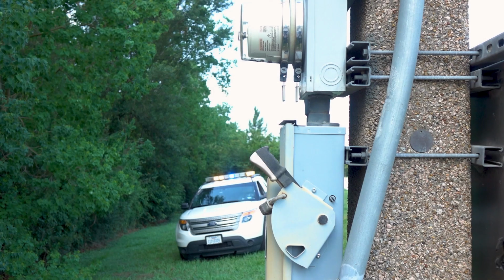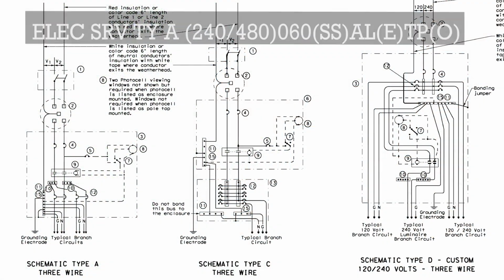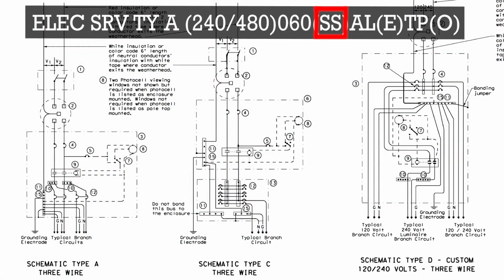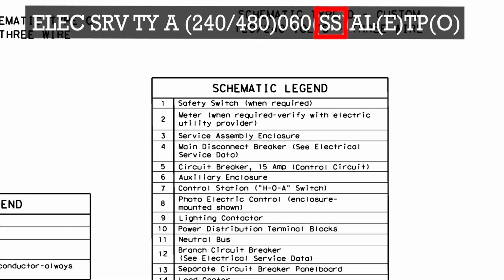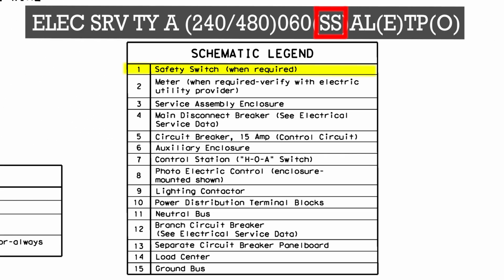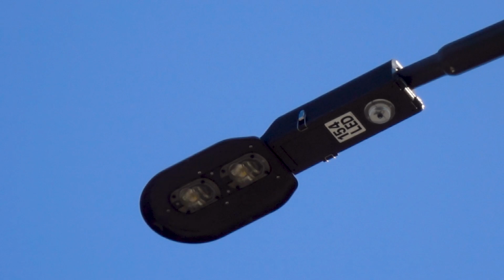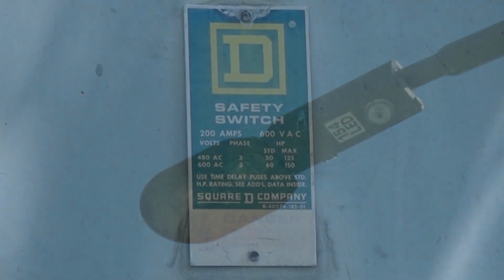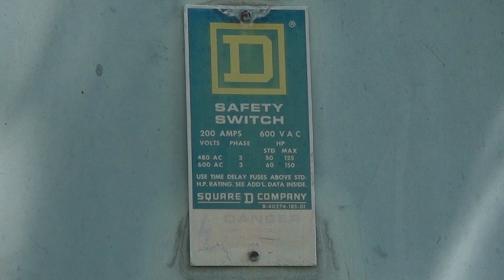This switch is called a safety switch and is designated by an SS in the 4th spot of the descriptive code on the plans. This switch is identified by the number 1 in the schematic legend on ED6. The switch provides a local means of cutting off power if the utility company needs to work on the meter. The switch must be rated for 600 volts.